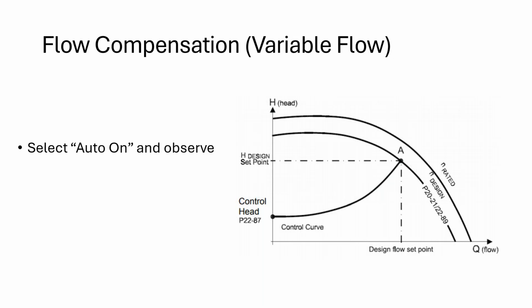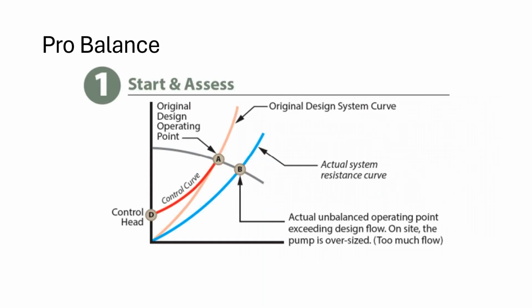So it's pretty straightforward, and if you observe the system while you're watching it, right? And then what happens is most of the time you end up running out on the curve because there's not enough head loss in the system. Actual unbalanced operating point exceeding design flow. On site, the pump seems oversized, too much flow. That's what it seems like, but that's because your system resistance is now further out on the curve, okay? The original design curve is at point A, and now the pump is trying to run at point B. So that's not where we want it to run because you're too far out, right? Instead of that 300 GPM, maybe you're getting 400 GPM, and that's not good for the system.